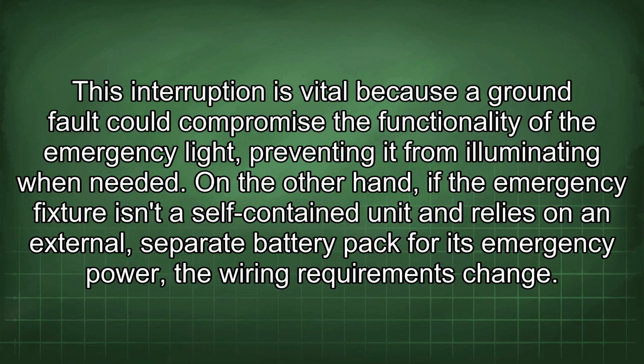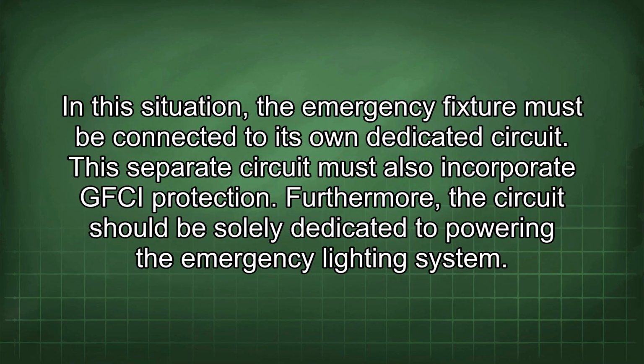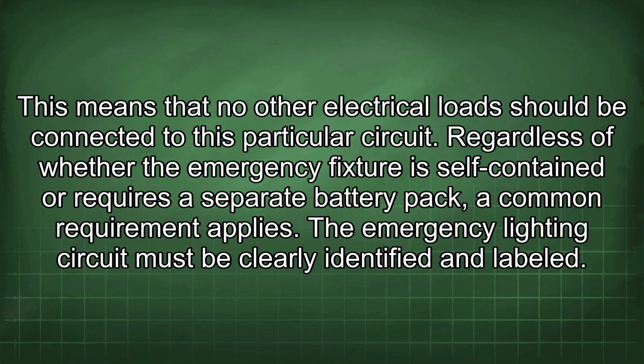external, separate battery pack for its emergency power, the wiring requirements change. In this situation, the emergency fixture must be connected to its own dedicated circuit. This separate circuit must also incorporate GFCI protection. Furthermore, the circuit should be solely dedicated to powering the emergency lighting system. This means that no other electrical load should be connected to this particular circuit.